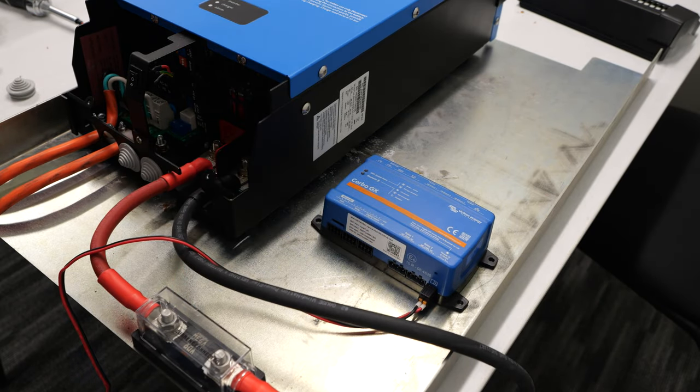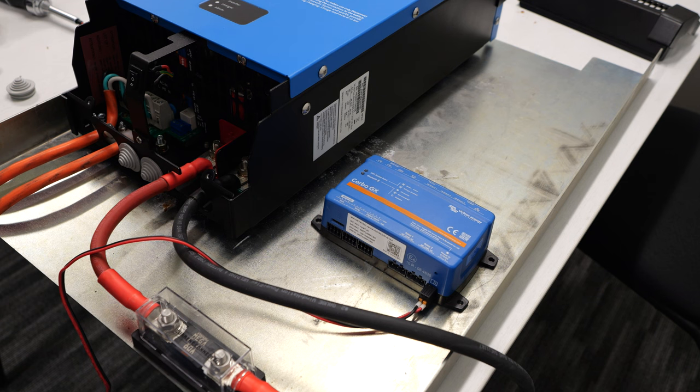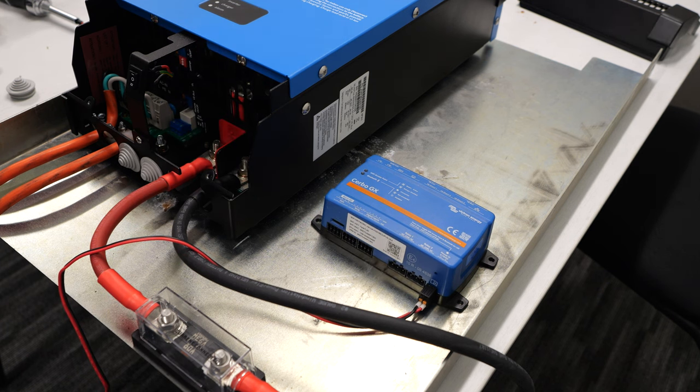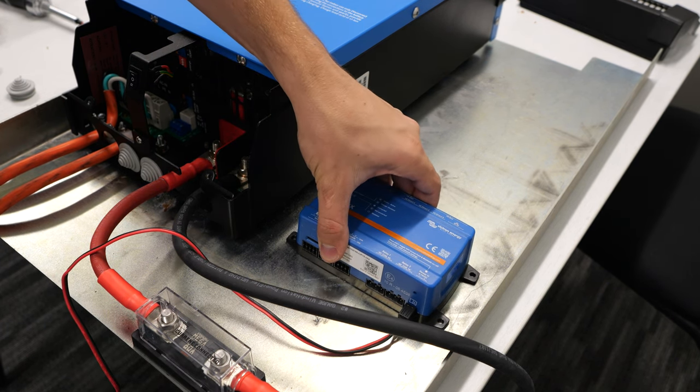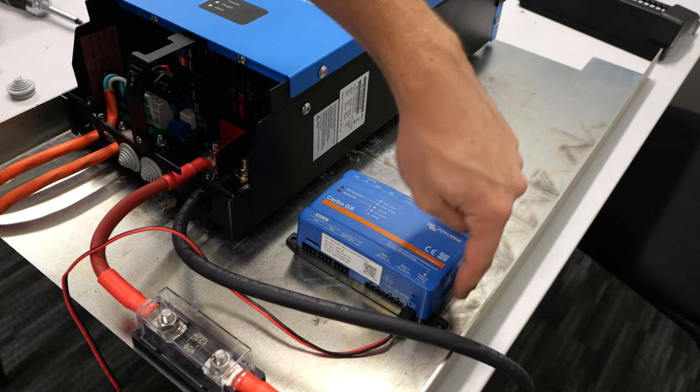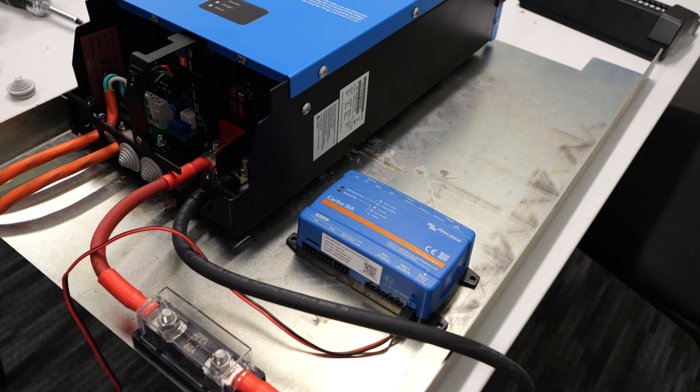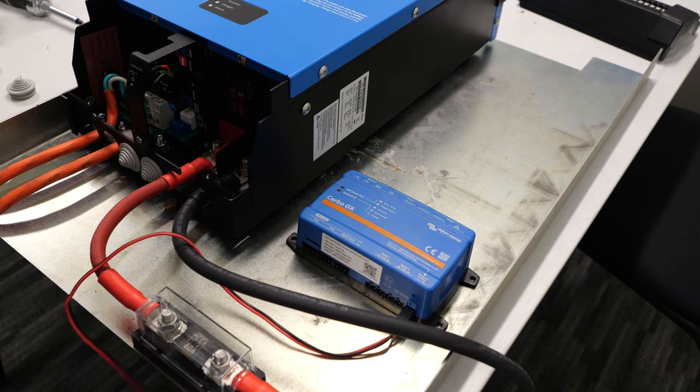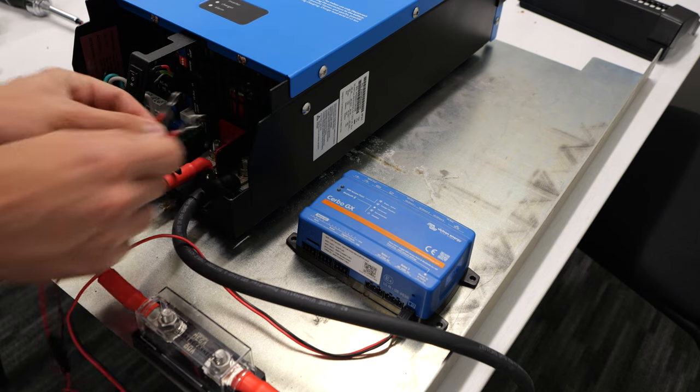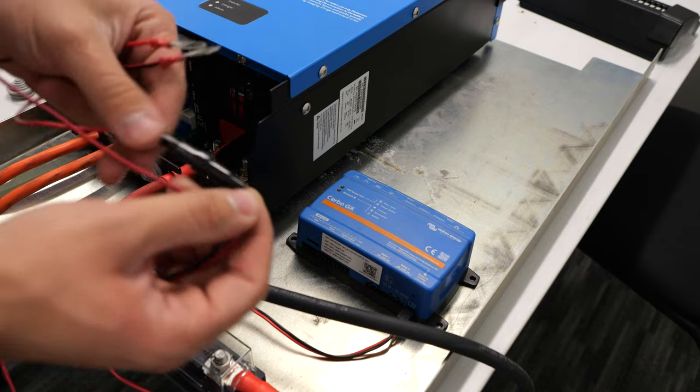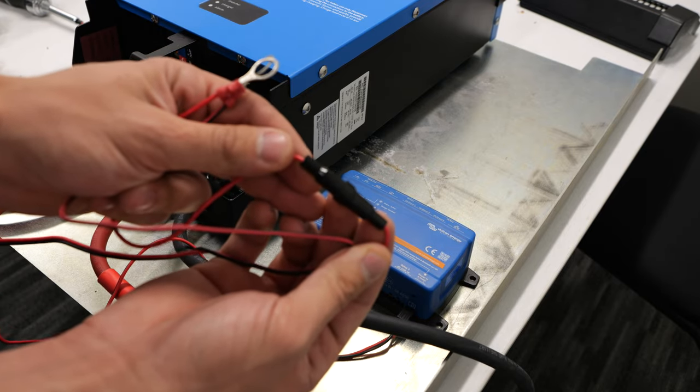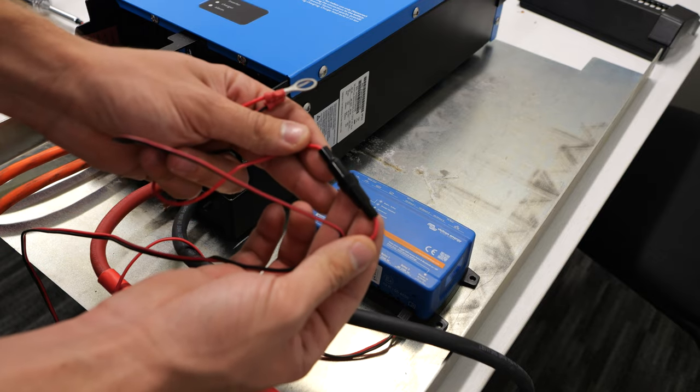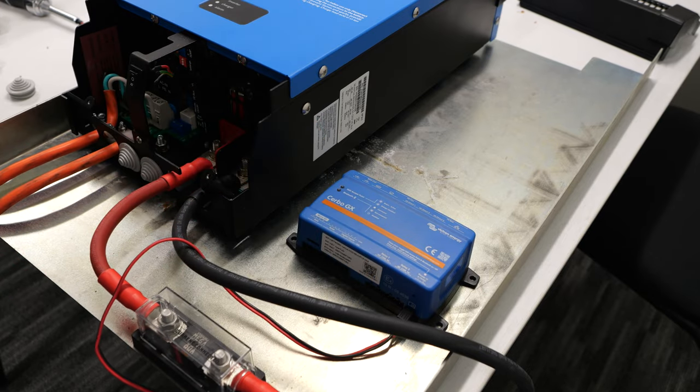Next thing I'm going to mount is a Cerbo GX so that we can monitor this whole system from anywhere in the world through the internet. I'm going to put it approximately right there. There are just four screw holes on it that hold it down to the plate, using some sheet metal self-tapping screws. There is a red and black cable. I'm just going to put this on the terminals in the inverter to give this power. This cable has a little fuse holder built into it so it's properly protected from overcurrent.